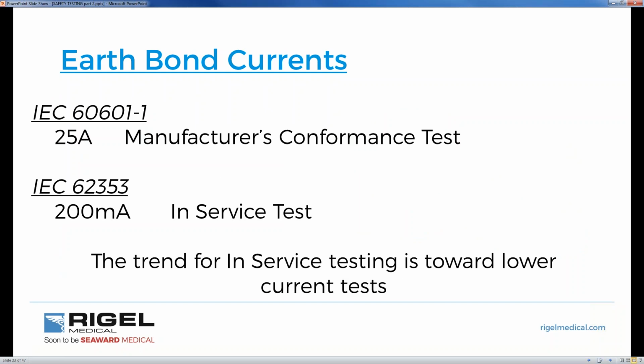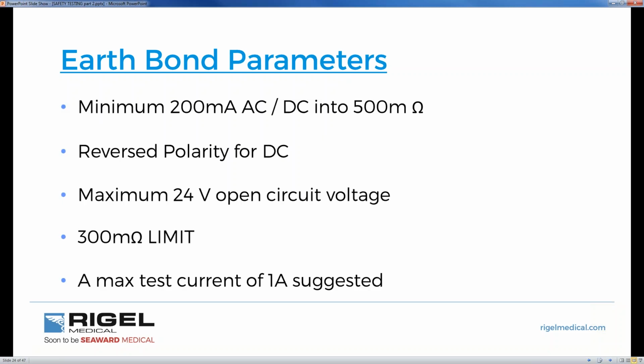Earth bond currents, a little bit of a, not so much a myth, but 60601 uses 25 amps, which is effectively a stress test. And this is part of a manufacturer's conformance test, almost like a type test. 62353 adopts 200 milliamps for in-service test. The trend for in-service testing is towards lower currents, and we went over that in the first part of the seminar. So if you want to remind yourself of those methodologies, watch the first part of the seminar where I go into depth between 25 amps and the benefits of using 200 milliamps. These are some of the characteristics that are further stipulated within the standard. Just to reiterate the points of earth bonding, notice that the pass-fail limit is slightly larger in 62353 than it is in 60601.